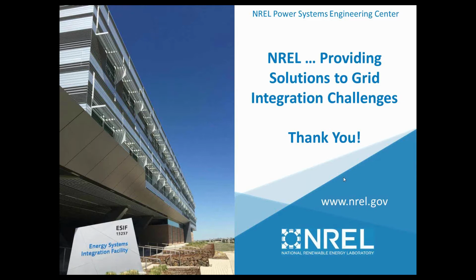I definitely would not say that once you're using that screen and you get to the load generation test, you would immediately want to use direct transfer trip. Direct transfer trip is an expensive option, and you have to look at how you're going to pay for that, whether it's utility provided or customer provided. It's still going to be fairly expensive. So I think you'd have to look at additional factors that may help you determine whether or not you need to require some form of embedded communications.